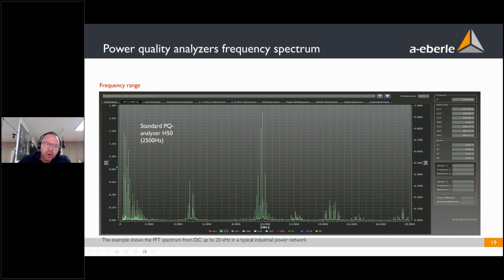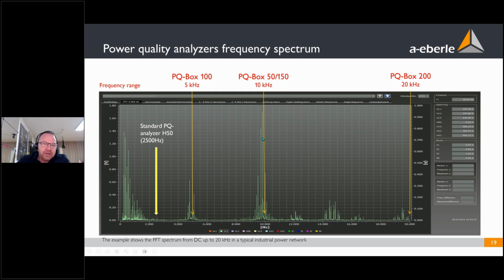And here in the lower harmonics, we see the typical harmonics. In addition to the harmonics, we analyze a 5 kilohertz, a 10 kilohertz, 15 and 20 kilohertz disturbance in our network. The highest value we can see is at 10 kilohertz with about 1.7 volt. So most of the power quality analyzers are completely blind for this kind of disturbance. Most of the power quality analyzers nowadays measure only up to the 50th harmonic of voltage and current. And here are the limits of our PQ-Boxes. The 150 can see the 10 kilohertz, but only the PQ-Box 200 can measure up to 20.